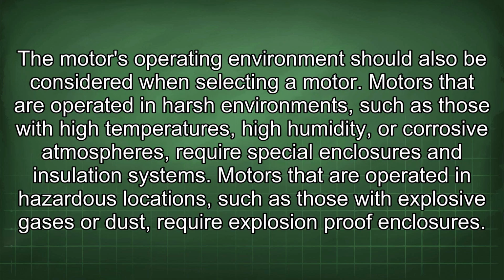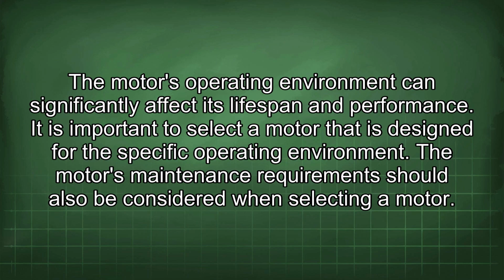The motor's operating environment should also be considered when selecting a motor. Motors that are operated in harsh environments, such as those with high temperatures, high humidity, or corrosive atmospheres, require special enclosures and insulation systems. Motors that are operated in hazardous locations, such as those with explosive gases or dust, require explosion-proof enclosures. The motor's operating environment can significantly affect its lifespan and performance. It is important to select a motor that is designed for the specific operating environment.